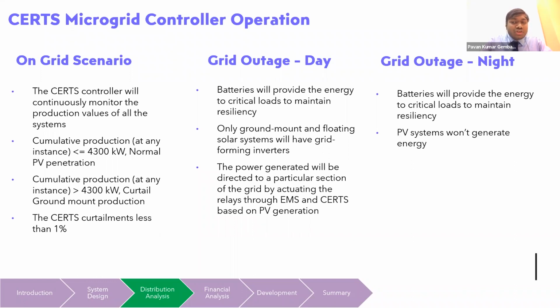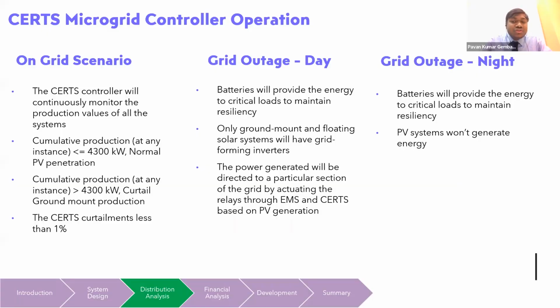In the grid outage scenario, the batteries will kick in to maintain the resiliency for the critical loads and provide a ride through for them. Only the ground mount and floating solar are equipped with grid forming inverters, and the energy generated would be directly directed towards a specific section of the grid using our energy management system, based on the demand and the PV generation at that point in time, using the relays and circuit breakers. During the nights, only the batteries will provide resiliency, and the PV generation would be zero.